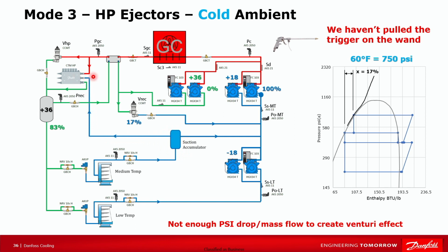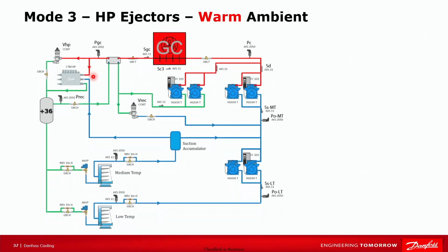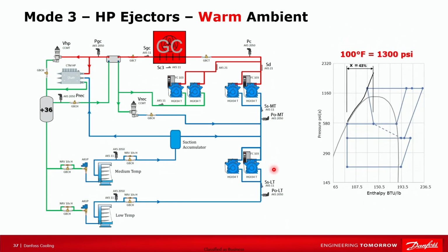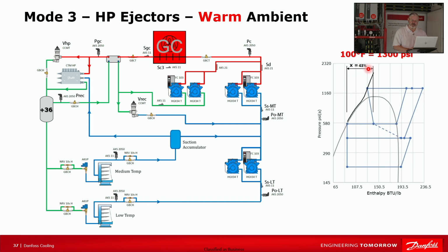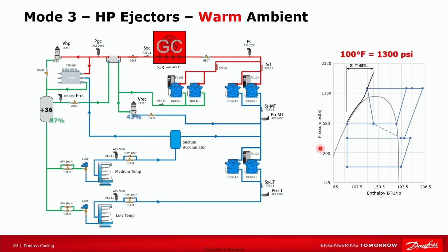Now let's look at this with a warm ambient. So now we're at 100 degrees. We're back to our 43% flash gas in the top of the tank and 57% liquid going out to serve the store. So we've already determined that sending that 43% to the plus 18 is a bad idea. We're going to move that up. And again, that flow is going to make its way over to our parallel compressors. However, since it's 100 degrees, we're using full operation of the ejector block.